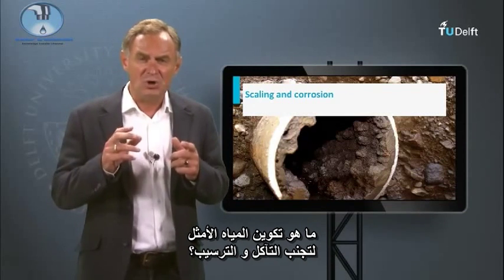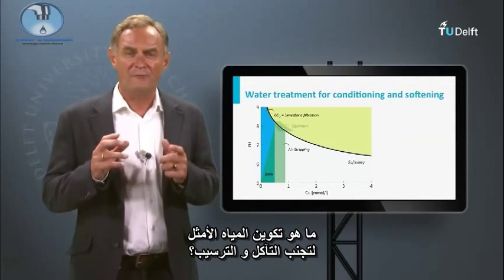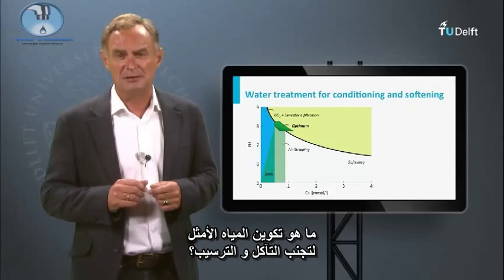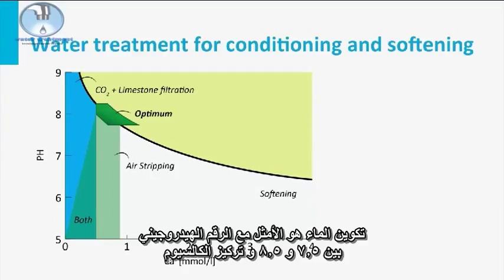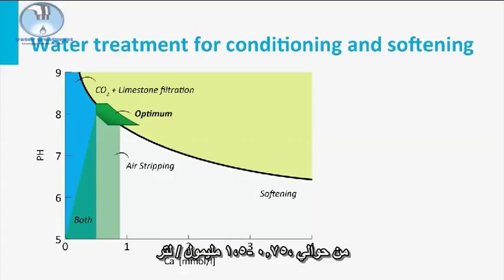What is the optimal water composition to avoid corrosion or scaling? The optimal water composition is with a pH between 7.5 and 8.5 and a calcium concentration between 0.5 and 1.25 millimole per liter, depending on the magnesium concentration. This gives a total hardness of about 0.75 to 1.5 millimole per liter.